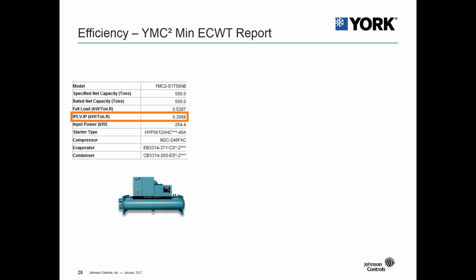So let's take a look at a specific chiller rating at 500 tons. So this is a YMC squared chiller at standard AHRI conditions. So 54/44 on the evaporator and 85/94.3 on the condenser. The IPLV you'll see here is a 0.3068.